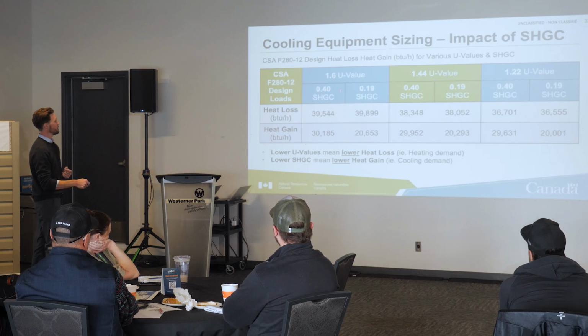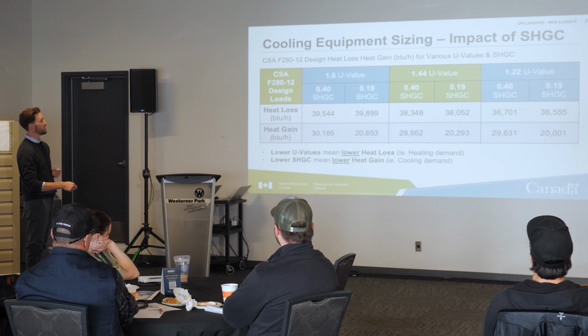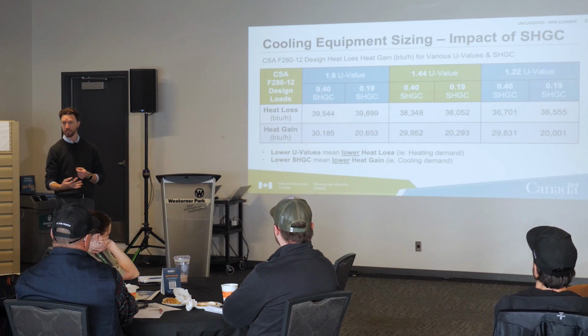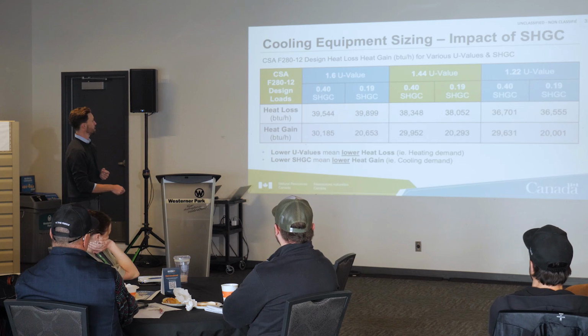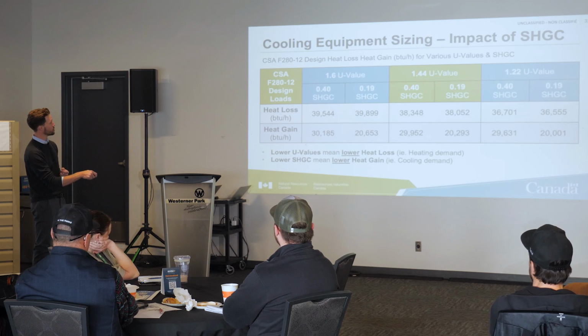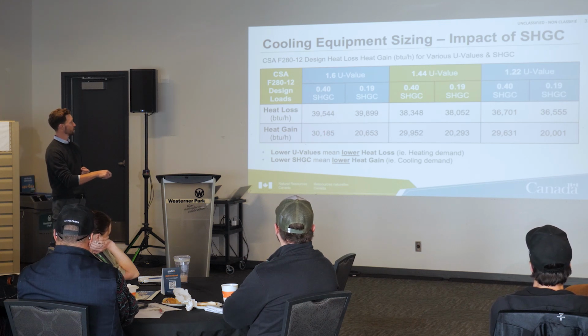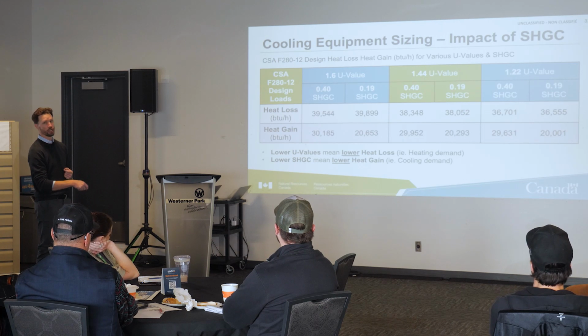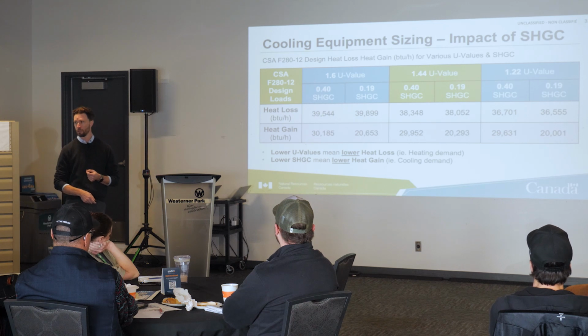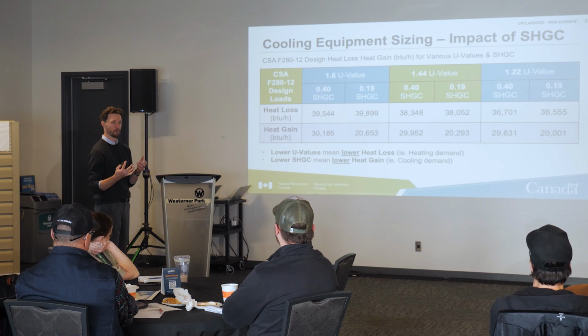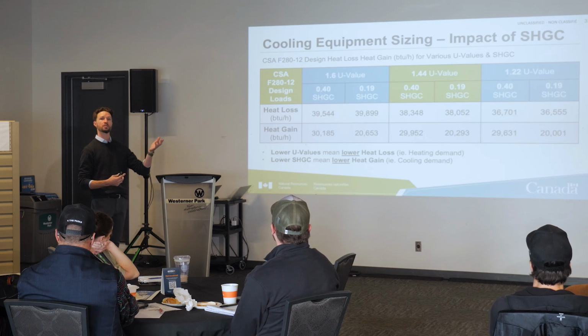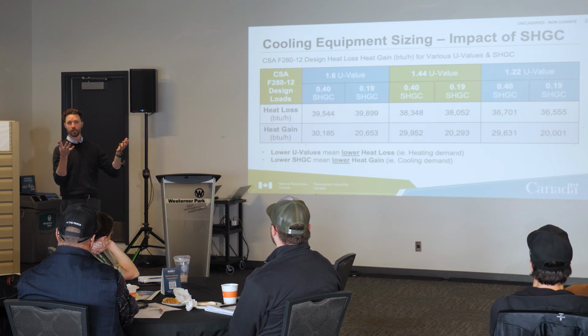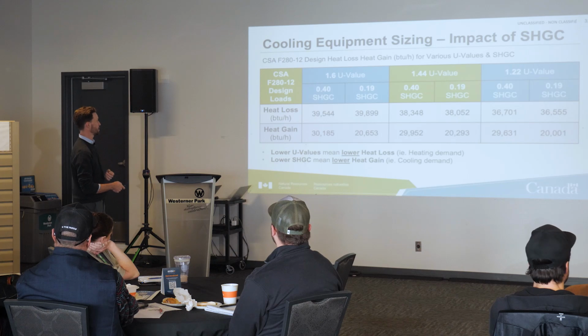On the other hand, if you look at the solar heat gain impact on heat gain, which defines your cooling system, your AC or your air source heat pump, you'll see that actually if you compare the 0.4s to each other, it hardly moves the needle at all. But what does move the needle is going from a high or mid to a low solar heat gain coefficient. It dramatically changes the heat gain profile of the house. So you can start to associate those things in your mind. U value affects my furnace and solar heat gain affects my air conditioner in terms of sizing, right?